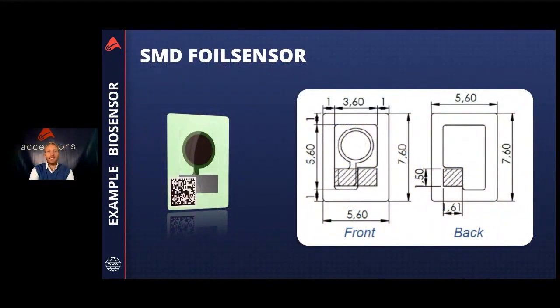If we go a little deeper into the layout of the foil sensor, this is our first layout for all these biosensors and ion selective sensors. Every ion selective sensor, pH, sodium, potassium, or every biosensor, will have the same diameters. This means that also for the pick and place process, often a fully automated process, you can use the same gripper to place the sensors. The outer diameters are 5.6 to 7.6.